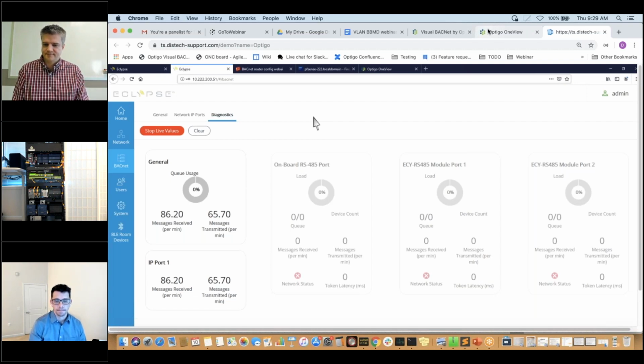Okay, can you not set up VLANs on layer 2 so you don't need a BBMD? And part of that is a comment that there are other providers that have secure VPNs that will communicate over layer 2. That's a great question, and that can absolutely be done. You can do layer 2 VPNs. I've done them myself. I've even bridged networks with layer 2 VPNs, and it does work. You can have that broadcast traffic come over. Depending on your manufacturer and how you set up your rules on your VLANs, you can potentially move broadcast traffic across VLANs.